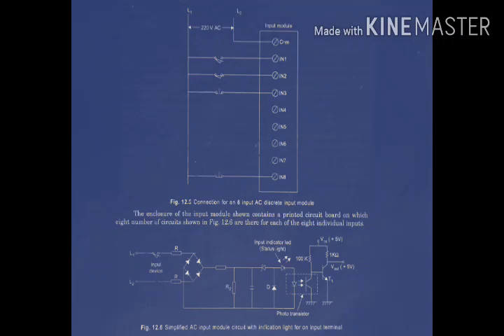Status indication — whether the input device is ON or OFF — is provided by another LED. You can see the status position that the input is ON. These are also used for troubleshooting. If the LED is ON, you can understand the input has been received. If the motor is not turning on, you can check whether the switch was pressed or whether there is a problem with the processor. This will also indicate the status of input and is useful in troubleshooting. Status lights are very helpful; the technician knows the status of all input devices just by looking at the status lights.